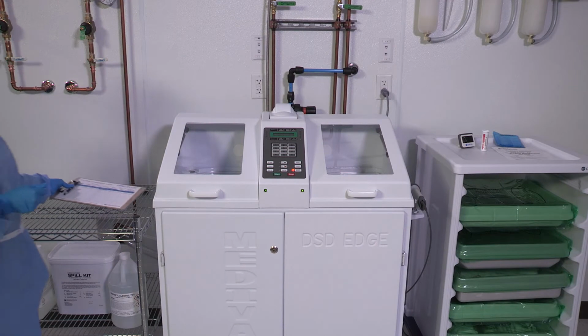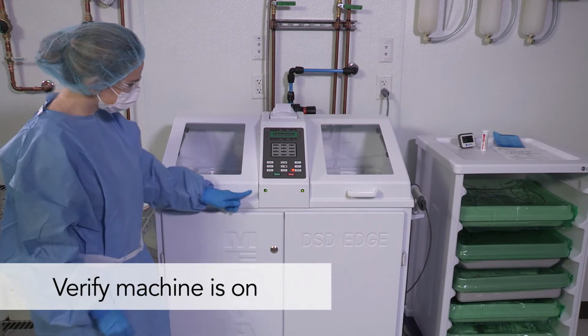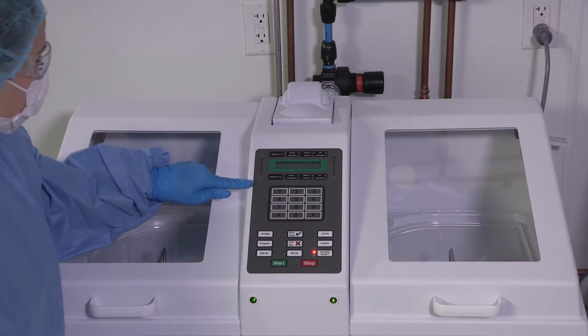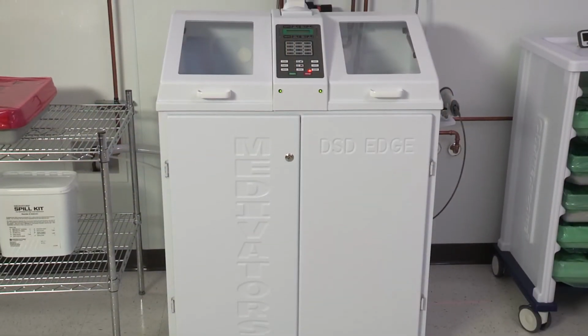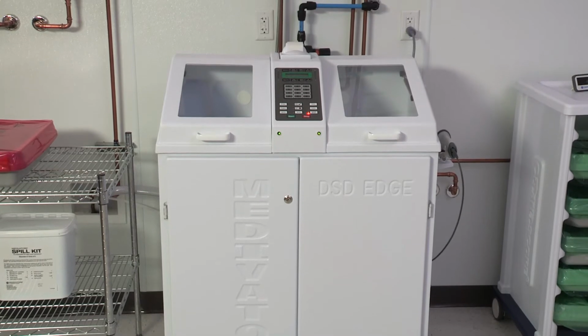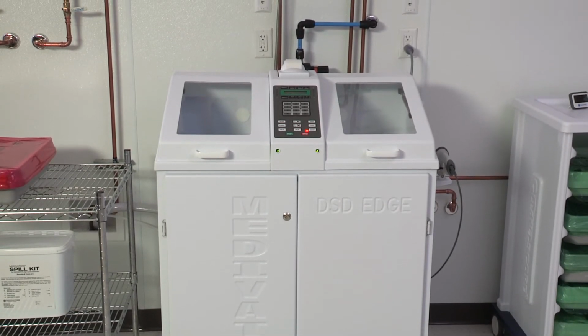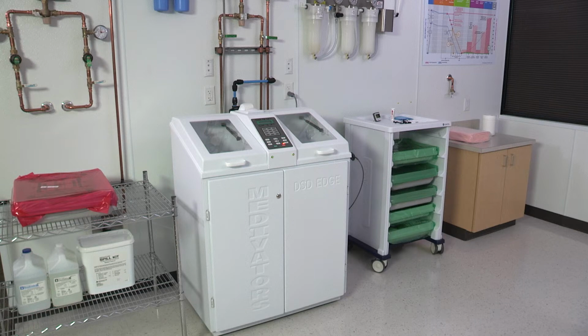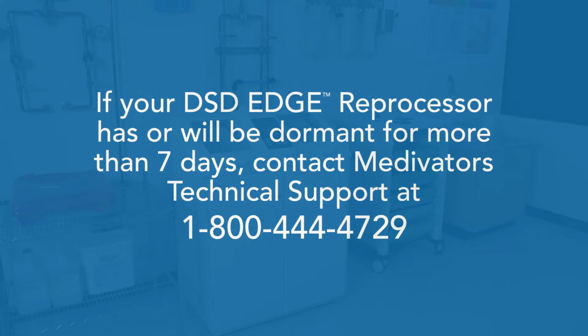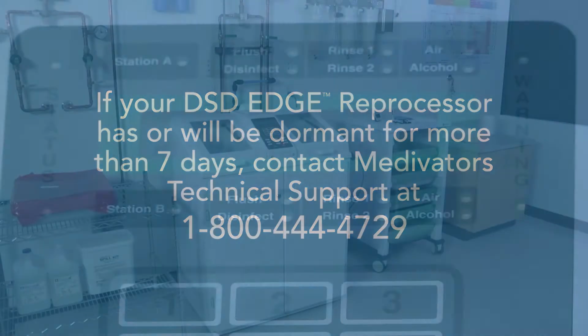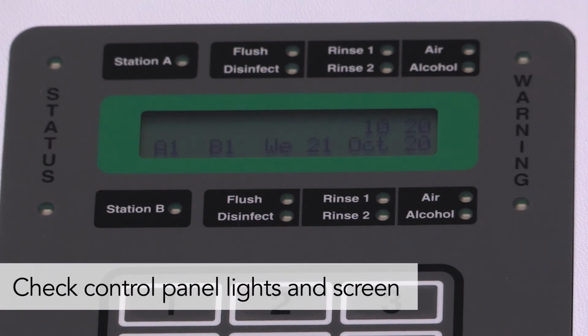At the start of the day, verify that the DSD EDGE Reprocessor is on by confirming the display area is illuminated. The unit does not have an on-off switch. If it is off, ensure the electrical plug is in a working receptacle. The AER should not be used if left dormant for more than 7 days. If your DSD EDGE Reprocessor has or will be dormant for more than 7 days, contact Medivator's technical support at 1-800-444-4729 for important instructions on restarting your AER. Check the control panel lights and screen for warning messages.